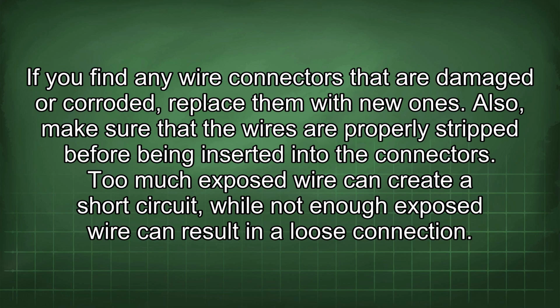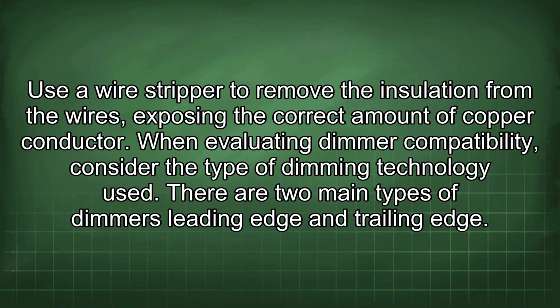Also, make sure that the wires are properly stripped before being inserted into the connectors. Too much exposed wire can create a short circuit, while not enough exposed wire can result in a loose connection. Use a wire stripper to remove the insulation from the wires, exposing the correct amount of copper conductor.